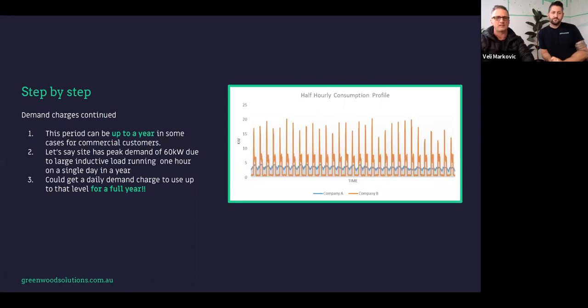So this is demand charge, which we've basically covered. You can get a daily demand charge for using up to a certain level all year, but just 10 or 15 seconds a day going over that limit is what they charge you on. It's like having a cutoff for your site consumption, and occasionally you spike above it. If you can reduce those spikes so they fall under the cutoff, your demand charge is reduced considerably.